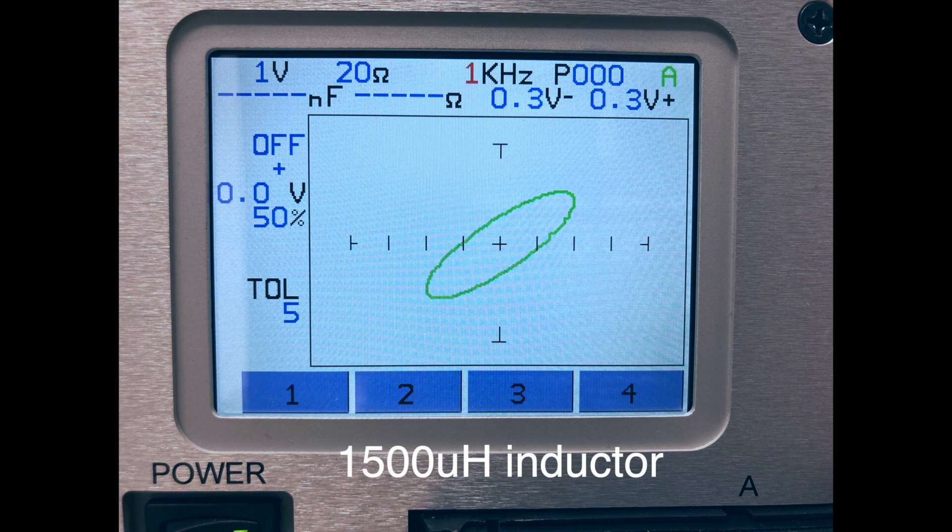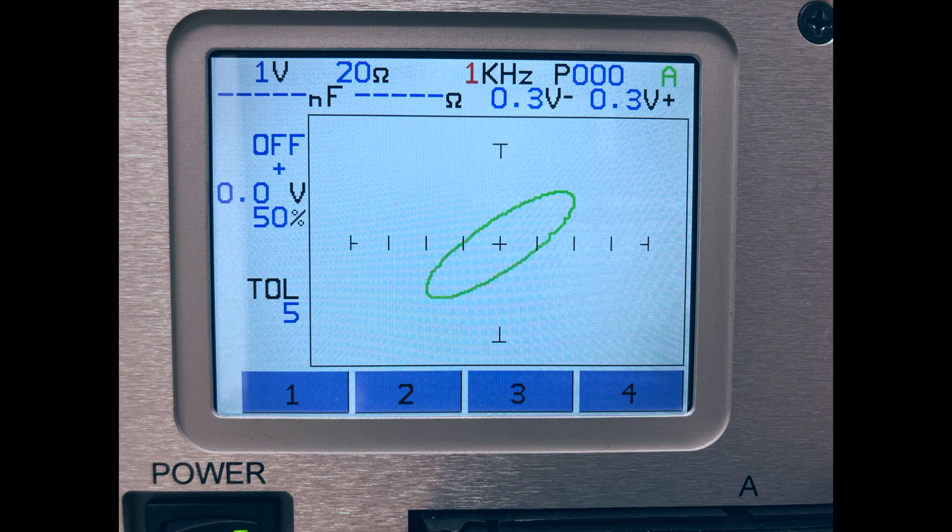Here is the signature of a 1500 µH inductor using the 20 ohm resistance and the 1 kHz frequency ranges. The ellipse width is a factor of the component value. The signature angle is a result of the wire resistance.